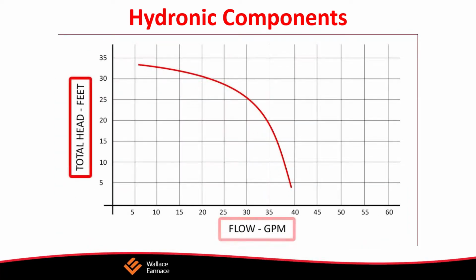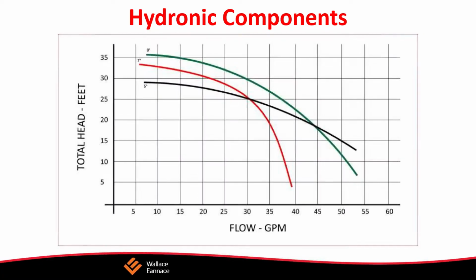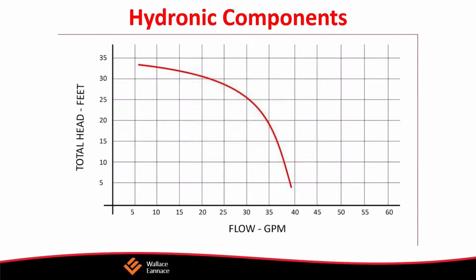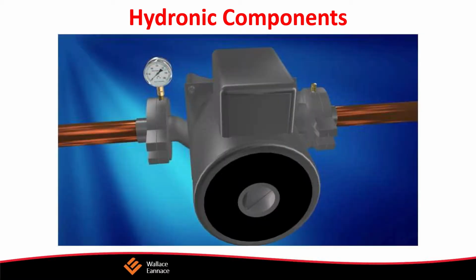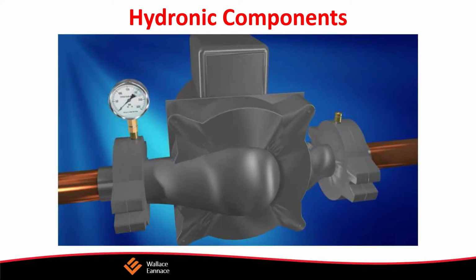Centrifugal pumps don't actually suck water. They're a change of pressure device, and high pressure will go to low pressure, and that's what makes the water flow. Water comes in through the eye and is forced out centrifugally through the volute. The force is measured in feet of water. Basically 2.31 feet is 1 PSI, so typically we talk about pumps in feet of head.